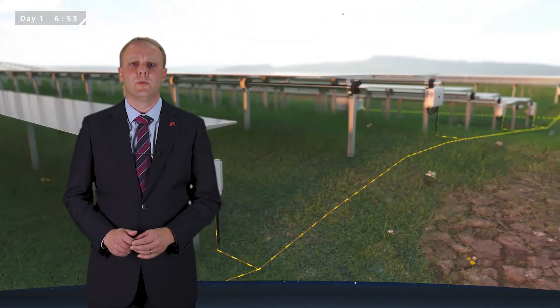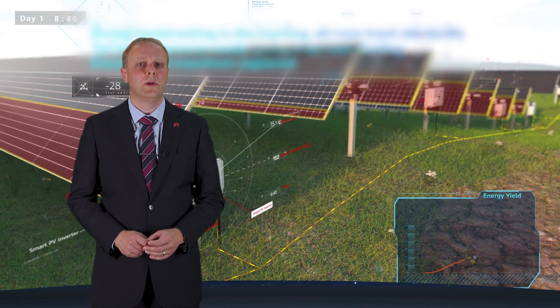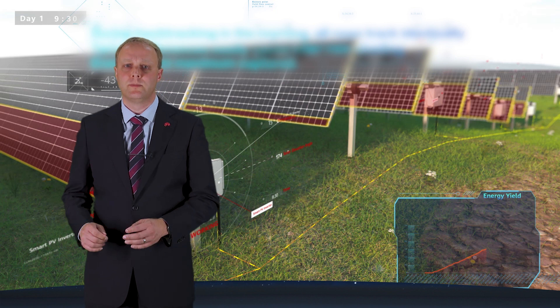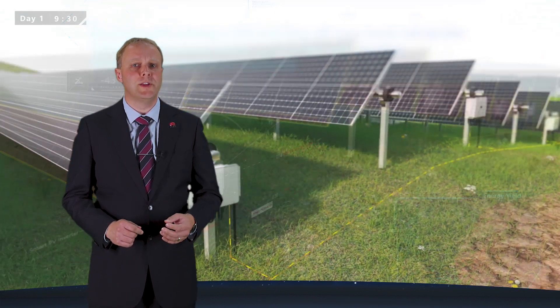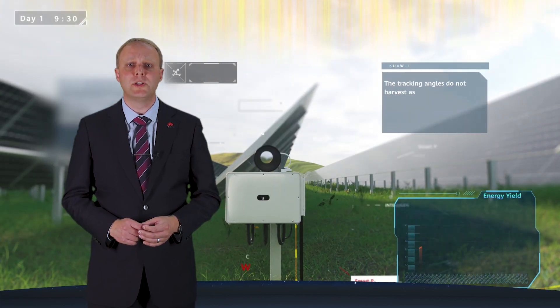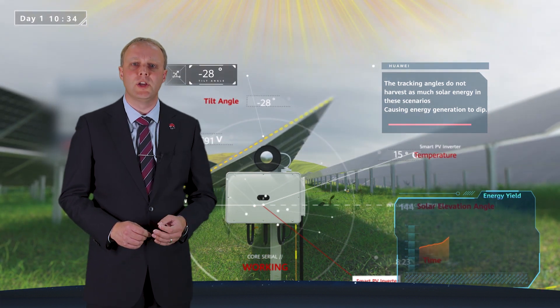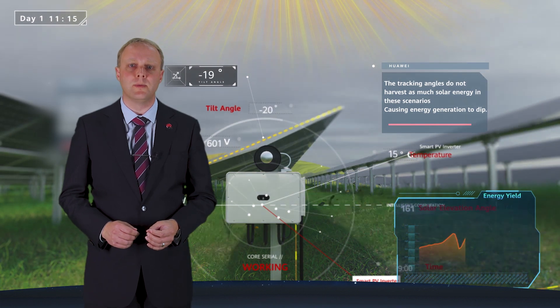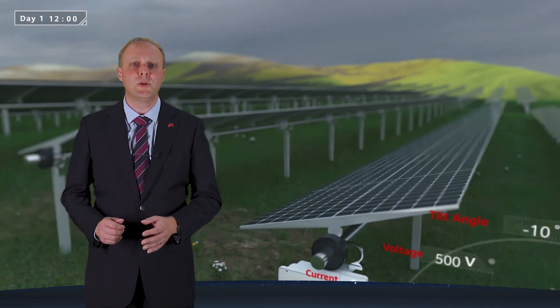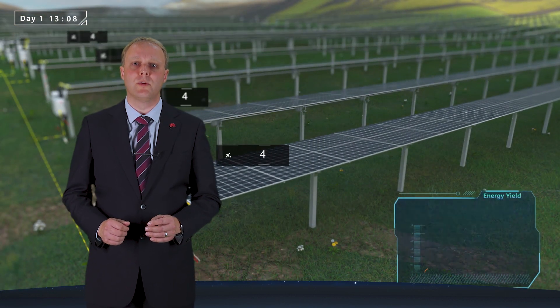Let's start with Huawei's smart tracker control algorithm. Conventionally, the module tracker system and the inverter are two worlds apart. Inside the tracker controller, conventional astronomical calculations and backtracking algorithms only try to follow the sun regardless of the conditions in the plant. In a row, shading can occur when the sun is low and the ground uneven. And in cloudy days, the tracking system is trying to follow a sun which isn't even there. And that is hardly the optimal way to harvest energy from the modules.